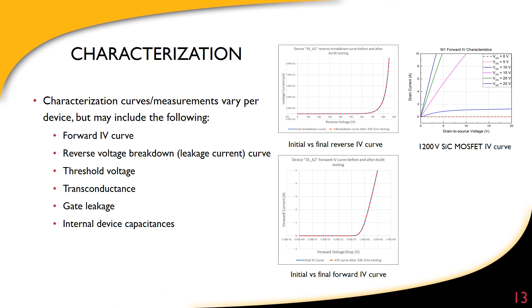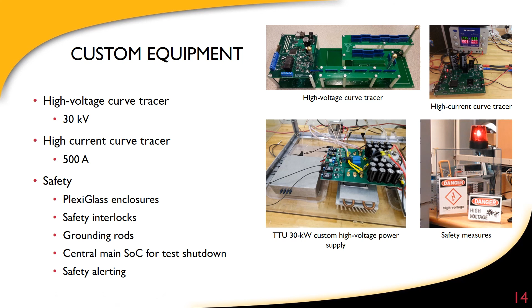For this testing, a lot of custom equipment was required because there isn't a very good market for this very high power testing at an accurate level. We used a high voltage curve tracer custom-built up to 30 kilovolts, a high current curve tracer up to 500 amps, and we built a lot of custom safety equipment, including plexiglass, interlocks, and ground rods, to keep protocols in place and keep people and the environment safe for workers entering and exiting.